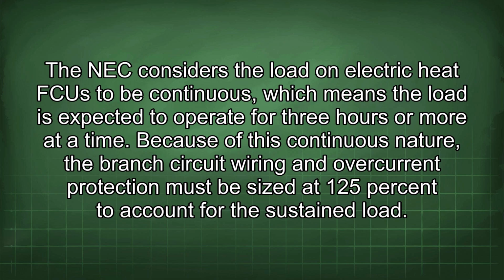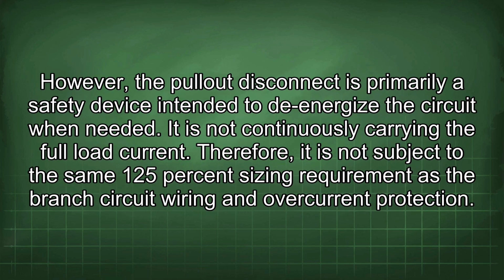Because of this continuous nature, the branch circuit wiring and overcurrent protection must be sized at 125% to account for the sustained load. However, the pull-out disconnect is primarily a safety device intended to de-energize the circuit when needed. It is not continuously carrying the full load current. Therefore, it is not subject to the same 125% sizing requirement as the branch circuit wiring and overcurrent protection.